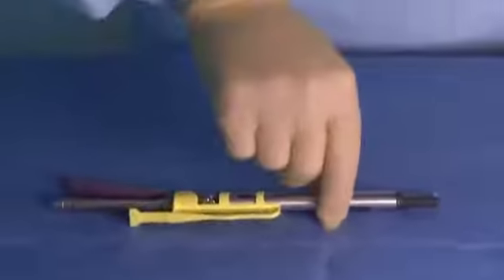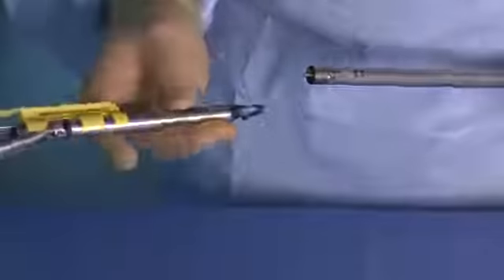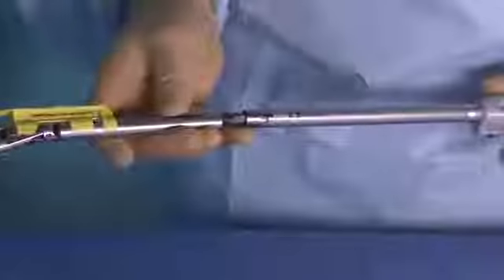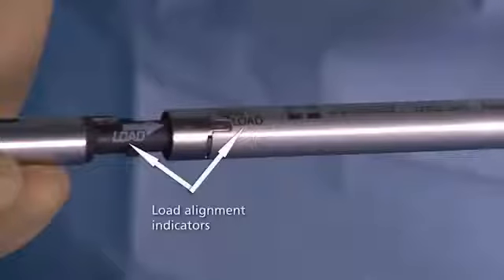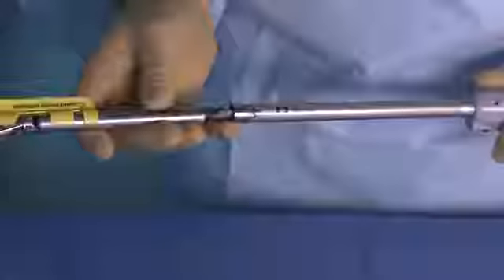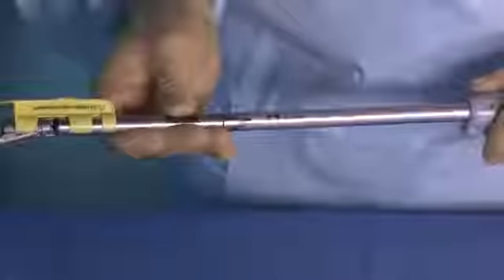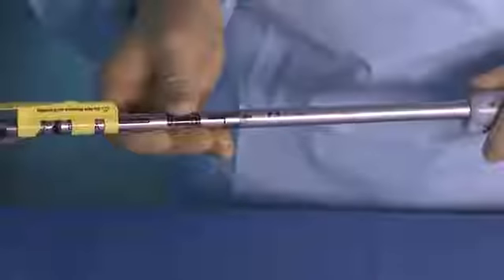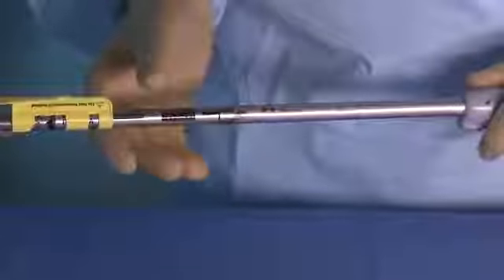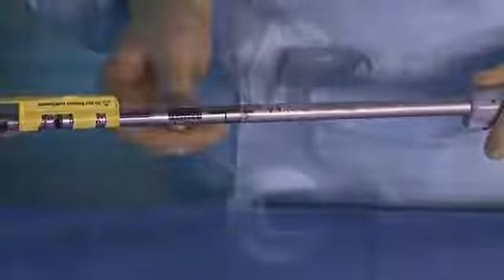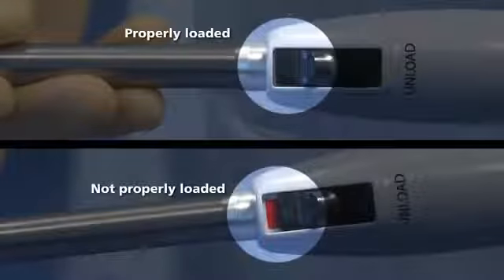Insert the pin located at the distal end of the Endo-GIA adapter into the proximal end of the reload. Ensure that the load alignment indicator on the reload aligns with the load alignment indicator on the adapter. Push the reload in and twist clockwise 45 degrees relative to the adapter, so that the reload will lock into place and an audible click is heard. When the reload is loaded properly into the adapter, the black Unload button will completely cover the red coloration underneath. The Unload button will not return to the fully seated position.